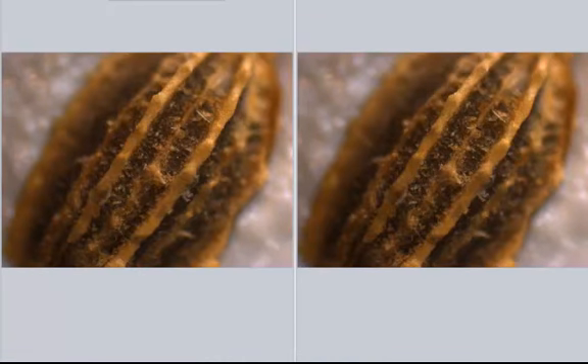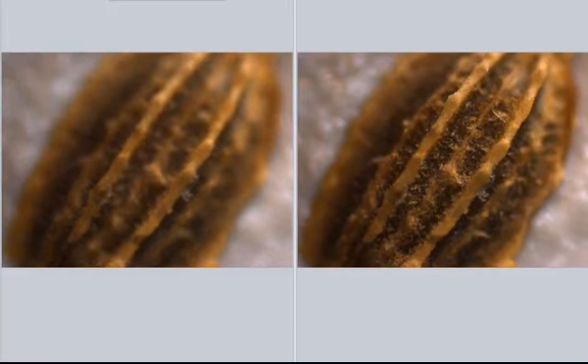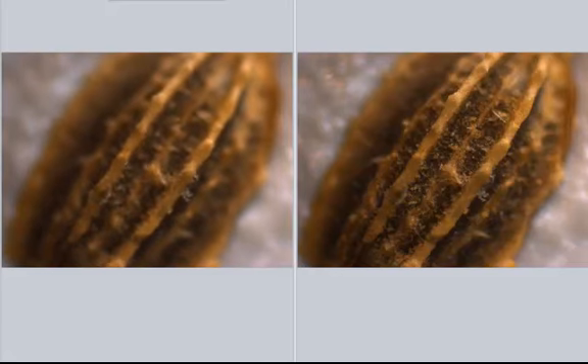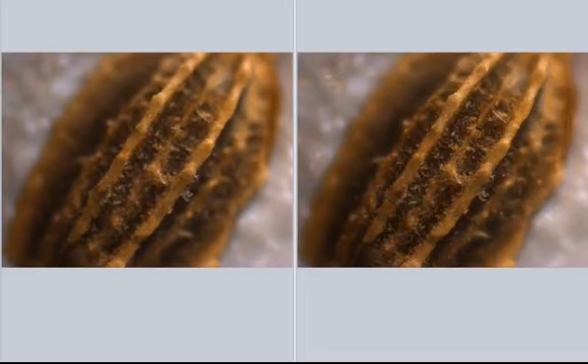I first start up the Live EDF module, and you notice on the left, I'm going to focus the microscope rather severely. You can see on the left, the image is still live. On the right is the EDFed image. So I am just going to simply grab the focus knob and slowly move it through the focus train.